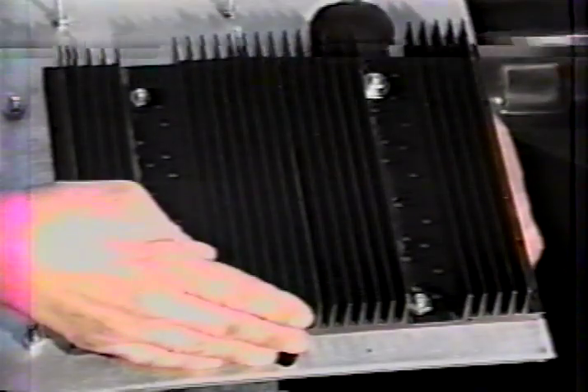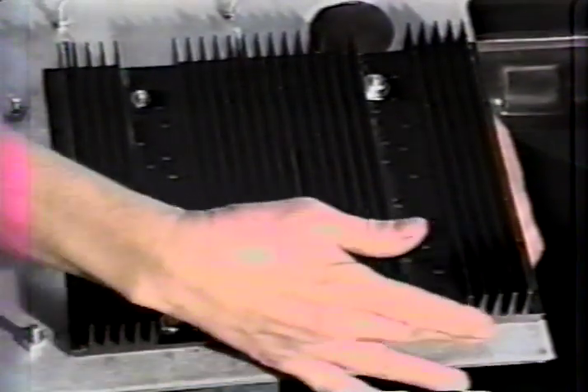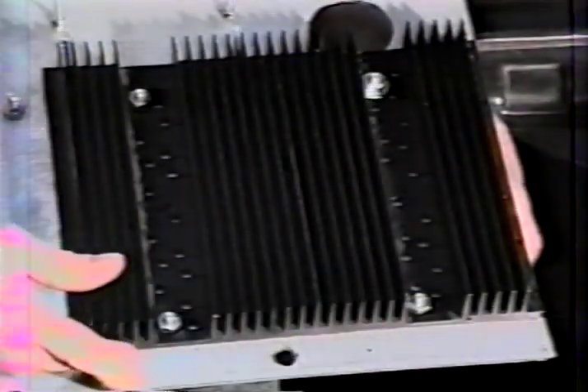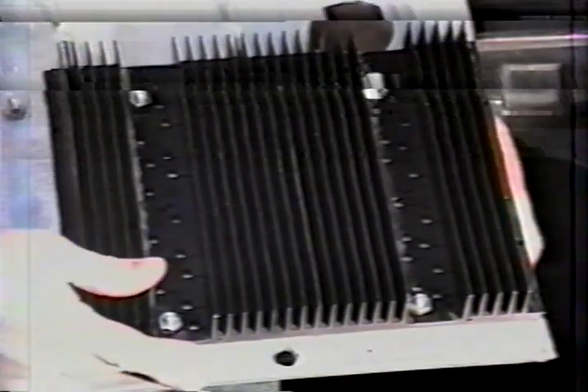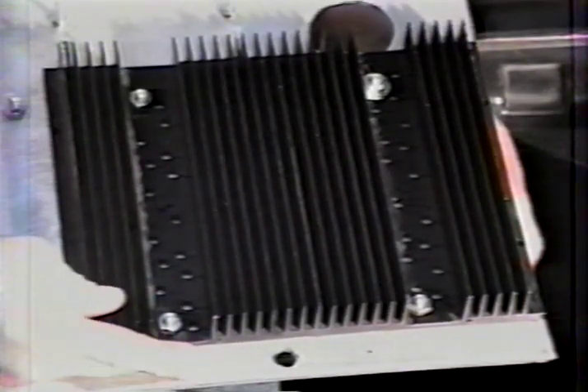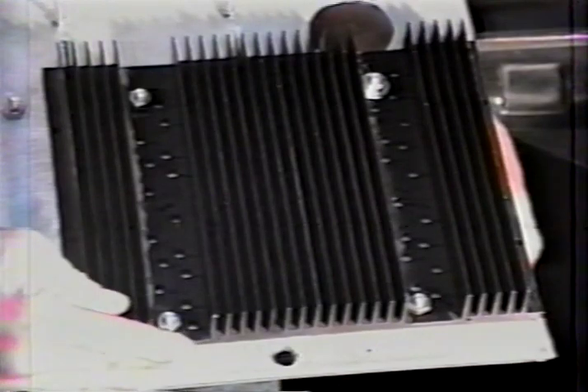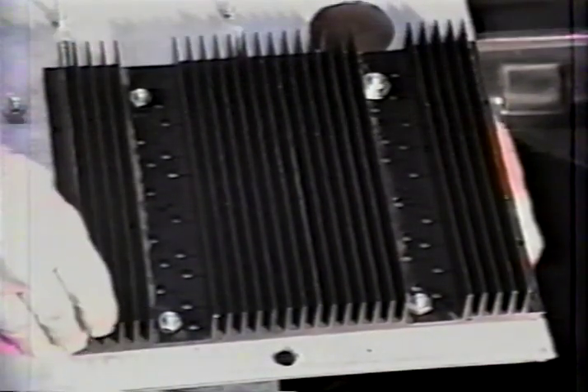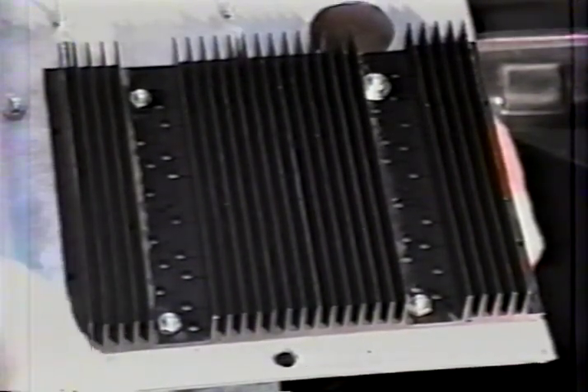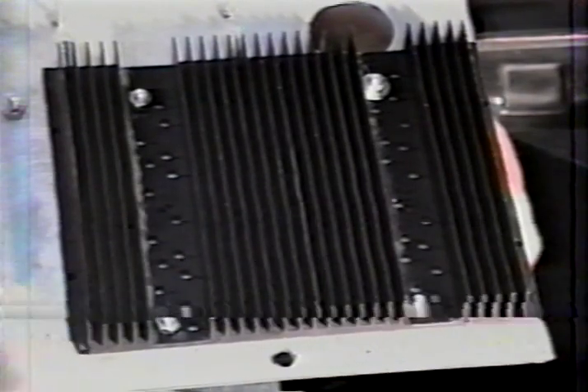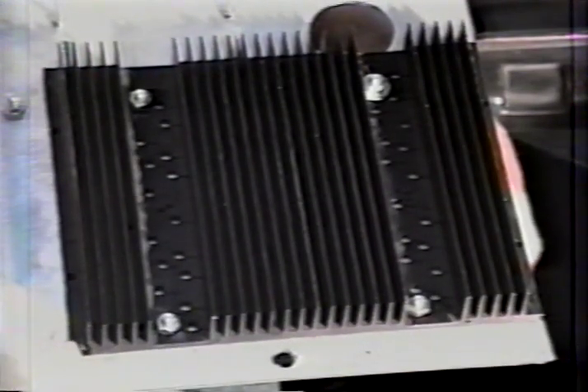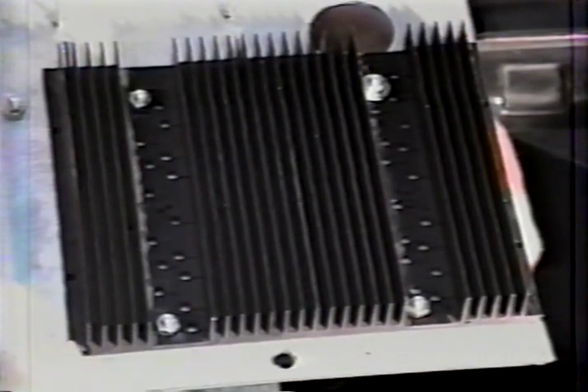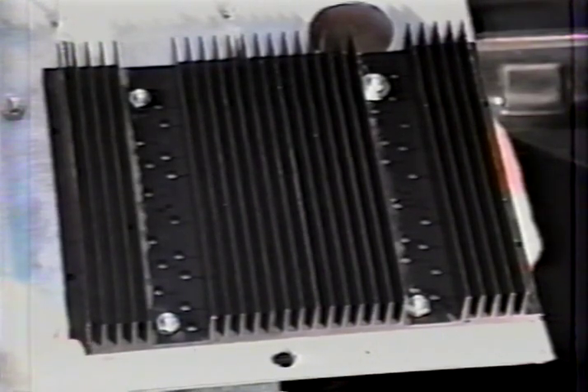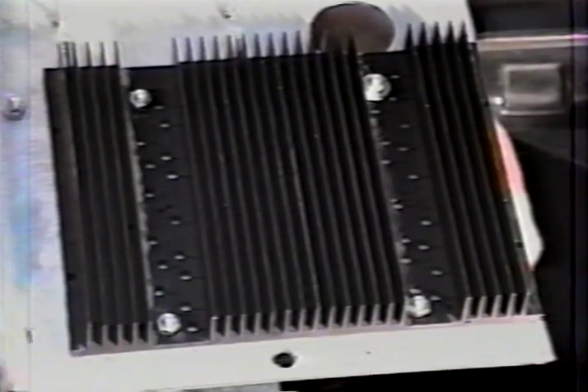The entire plate is isolated from the battery rack it sits on by a neoprene strip cemented to the plate across the side where it rests on the rack. In addition, the bolt that attaches the plate to the battery rack is isolated by the rubber on these isolating nuts, which we use to connect the plate to the battery with the bolt.